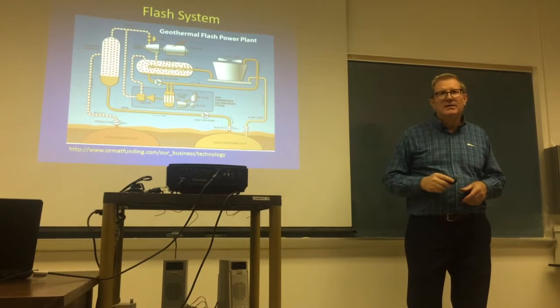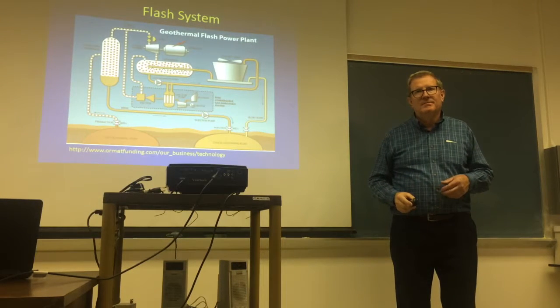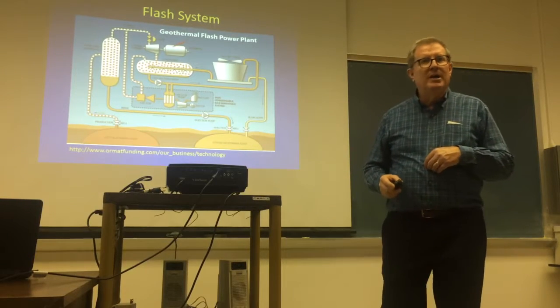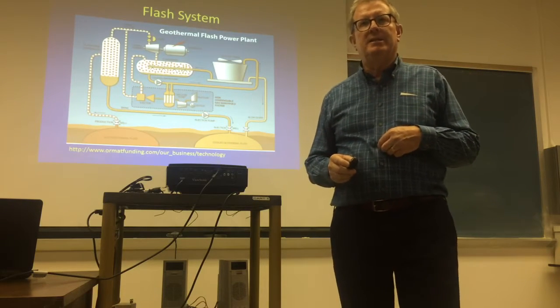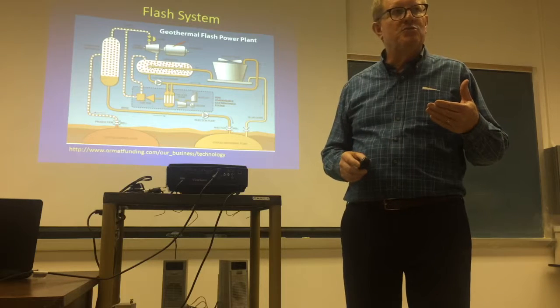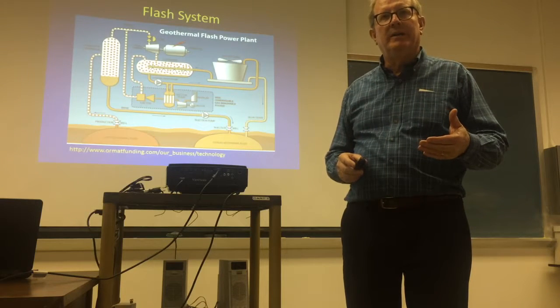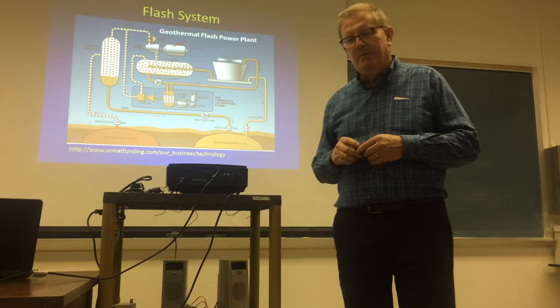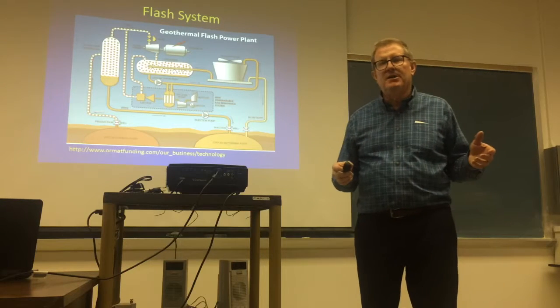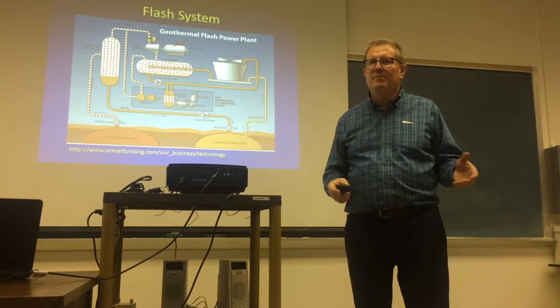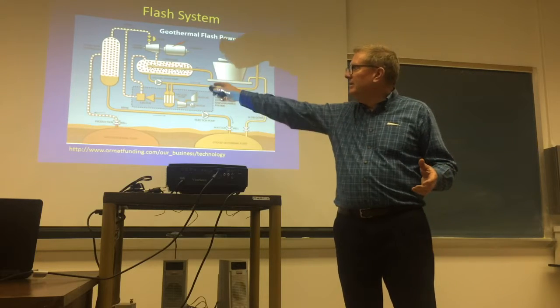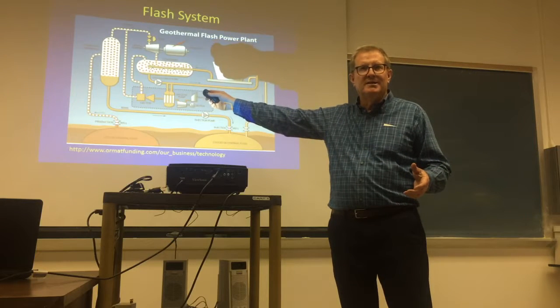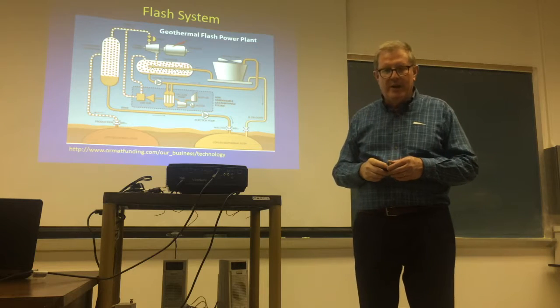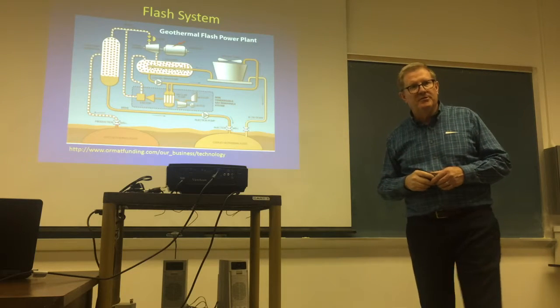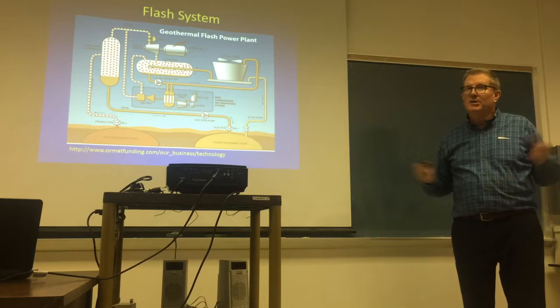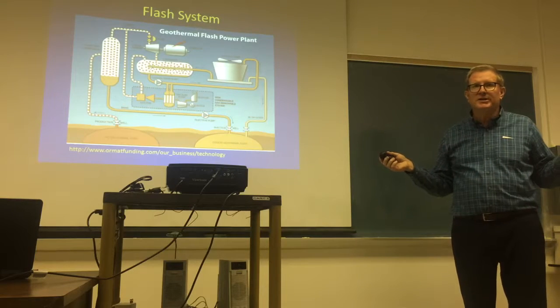Do you get scaling or mineralization inside the binary systems? No, not to any great extent that I've seen. Those systems run at very high reliability because they keep the hot water under pressure. I'm sure there's some, but nothing to the scale of this, because I've seen this out there where they have to shut down for weeks and descale the pipes before they start back up. But by keeping it under pressure, you never actually flash things and force it into saturation.